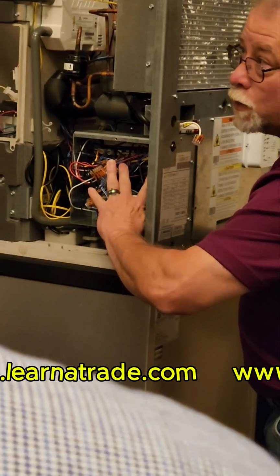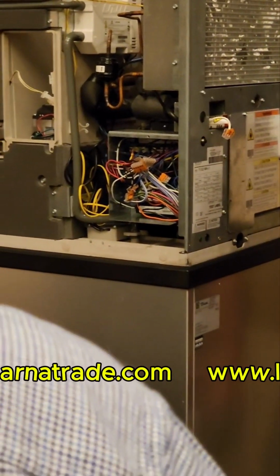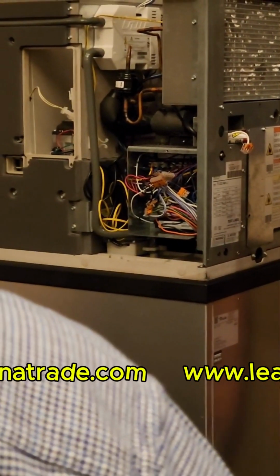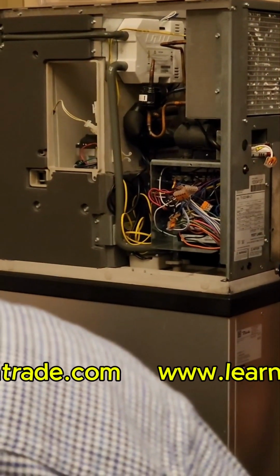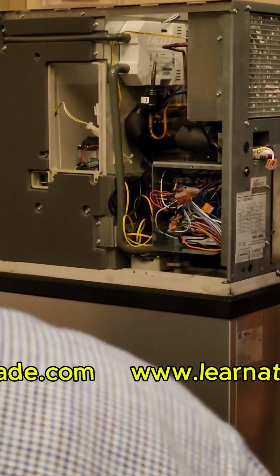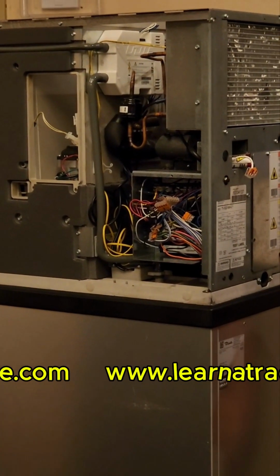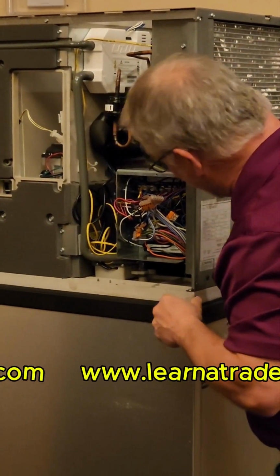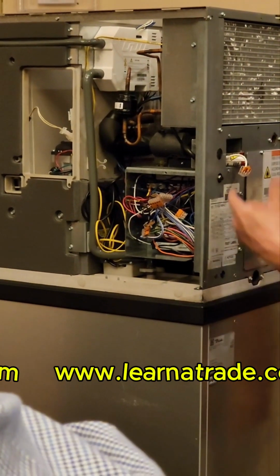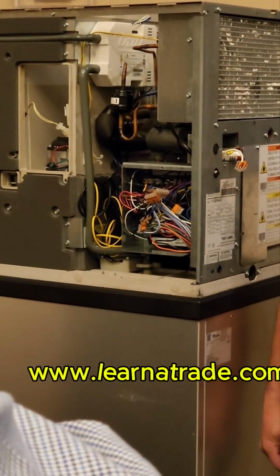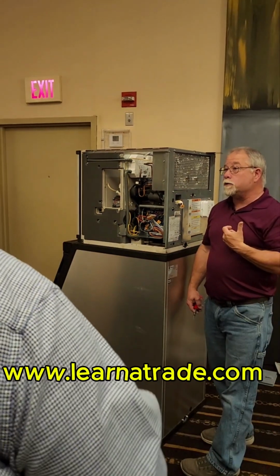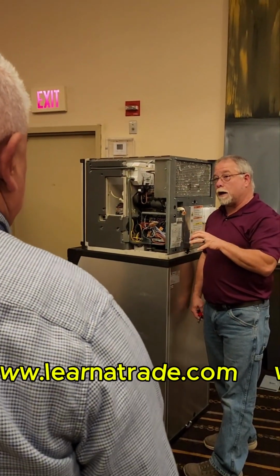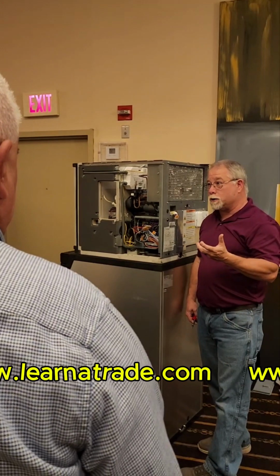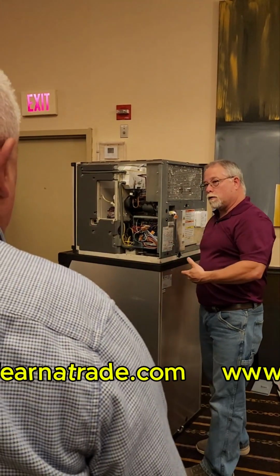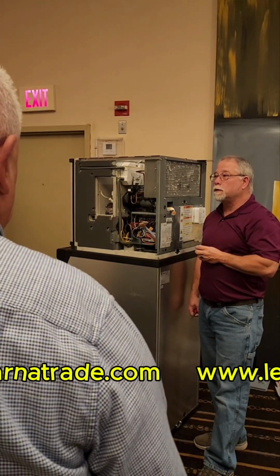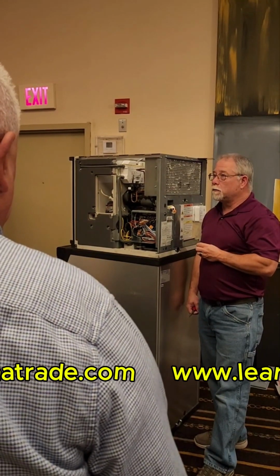That little white transducer has 8 little spider legs that are really flimsy and easy to break, holding it onto the board for communication. We're only using 3 of those prongs, I think, for communication. But if you just grab hold of that stuff and start pulling it out, you could pull that transducer off the board. If you break or damage those prongs so it can't fit back in, or it's one of the ones used for communication, you'll have to replace the whole board. You don't replace just the transducer, it's not a repair component.